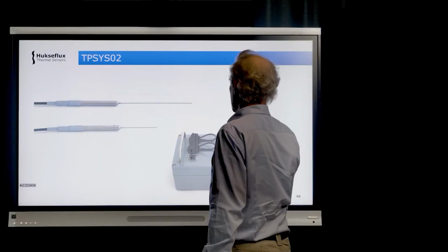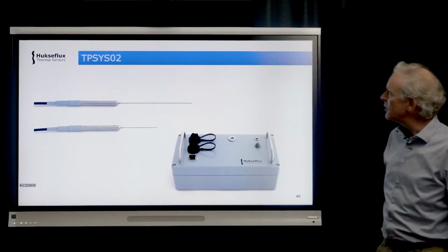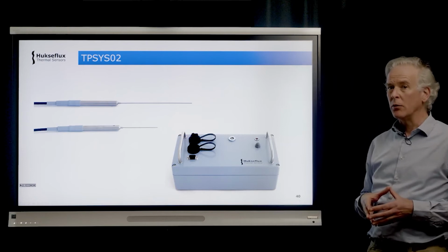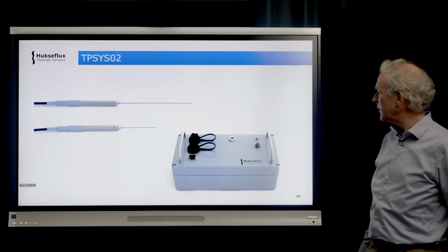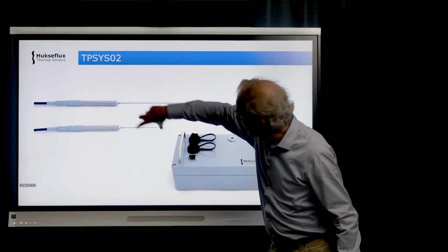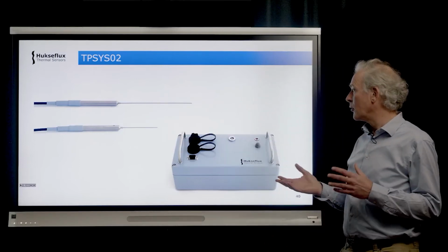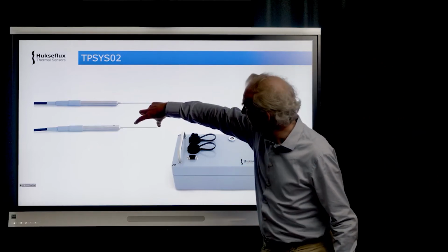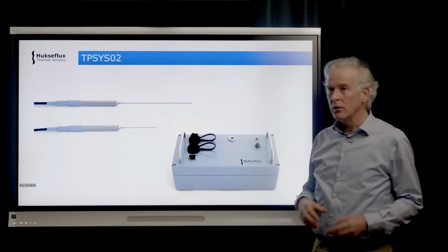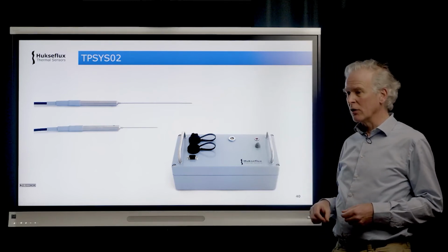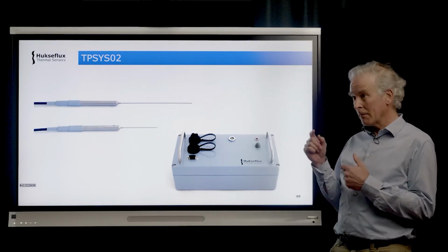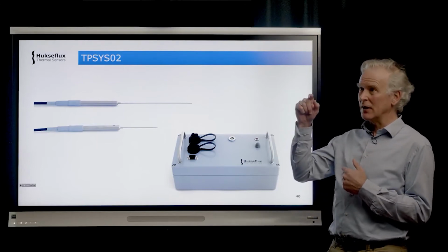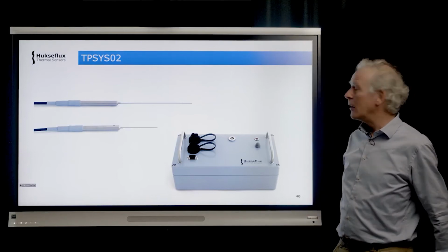We also have other systems, TP-Sys. They have very thin needles, about 1 millimeter, 1.6 millimeters. Also the needle length is smaller. An order of magnitude of 60 millimeters length is needed here as a minimum of insertion. The previous MTN needle was 100. The FTN was 170 millimeters.